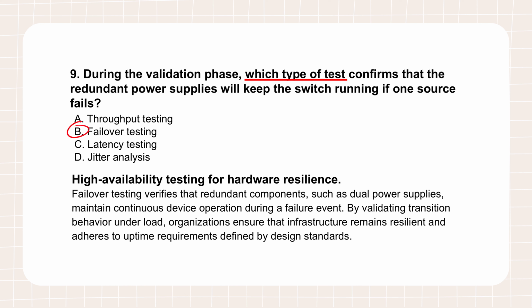It's crucial, and it's not just yanking a power cord out of the wall - it's a controlled test. You simulate the loss of the primary power source while the switch is actually passing traffic under load. The goal is to prove that it seamlessly fails over to the secondary PSU with zero interruption to the data flow. It's how you validate your physical high availability plan.